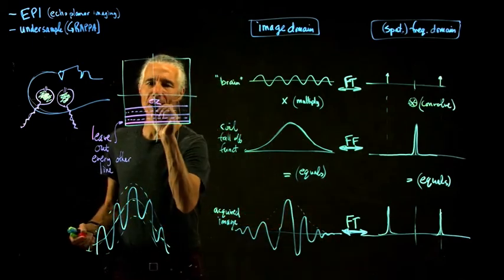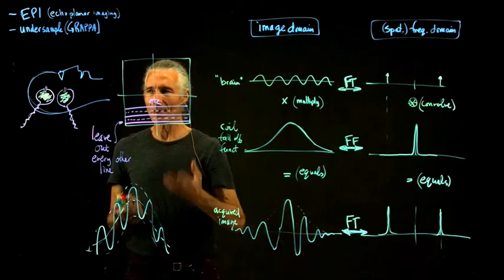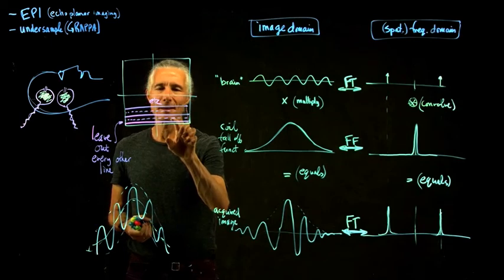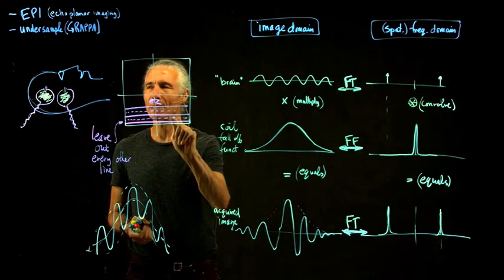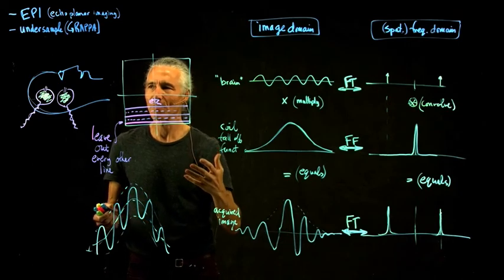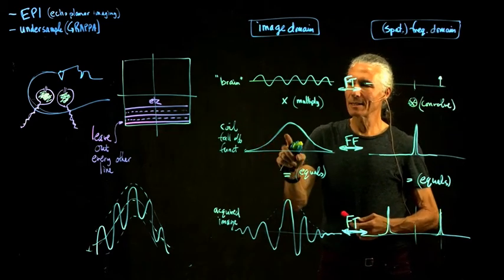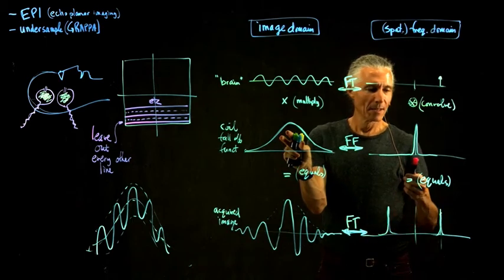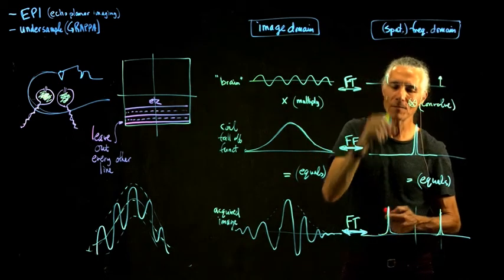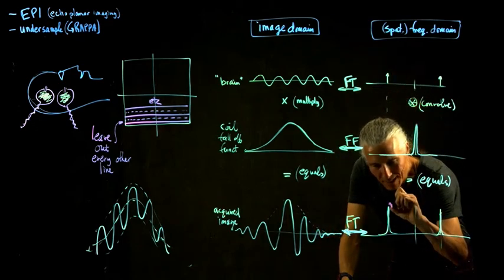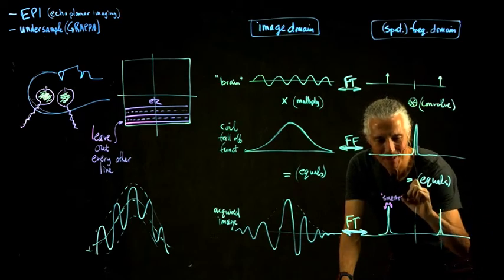That's good for us, because now we can get done in half the time. We've collected half as much data. It only takes half as long, and so we can collect twice as many slices. But if we have an orthogonal decomposition of k-space, we just left out half the data, and that data is all completely uncorrelated. So the data in this left-out line can't be predicted from the surrounding lines, because it's completely uncorrelated, because that's the definition of the Fourier transform. But now look what's happened over here. When we use a coil that has a local field of view, it takes the spike-like spatial frequencies in our image and moves them off to the side a little bit. It smears them out. Smear. I call that a technical term. It smears spatial frequencies.